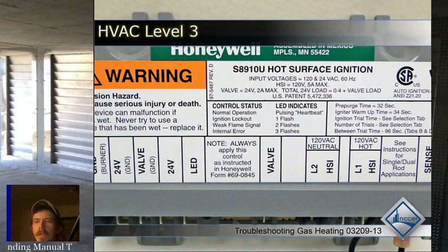stuck. The other thing you can do is obviously ohm out the coil. You should probably do that before trying to free it. Your steps should probably be verify voltage, check the coil and make sure it ohms out, that it's not shorted or open. Then if it's not shorted or open and the coil seems to be good, try and energize and de-energize the valve, and you usually can hear it click. So if you hear it clicking, then you know it's at least trying to move. So like I said, you can apply and remove voltage multiple times to try and free it up.